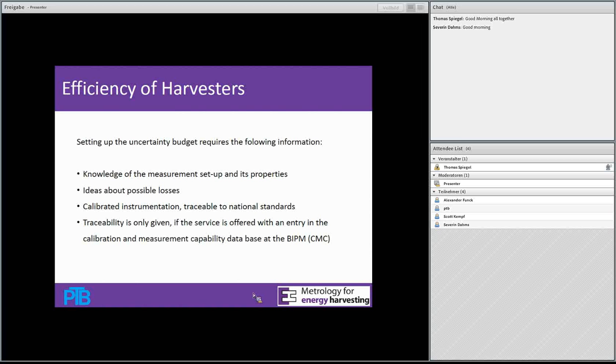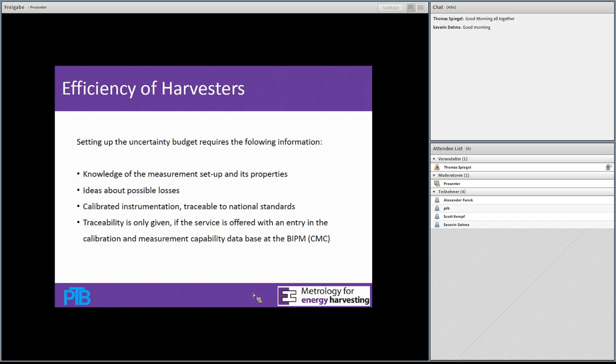For these types of measurements, you can set up mathematical equations describing the measurement process, which lets you build an uncertainty budget using all you know about the measurement setup and its properties, including ideas of possible losses, even if incomplete, you can still give estimates. You need calibrated instrumentation traceable to national standards and to the SI. This traceability only holds if the service is offered by an accredited calibration laboratory or a national metrological institute with an entry in the measurement capability database at the BIPM, which maintains the units for the world.